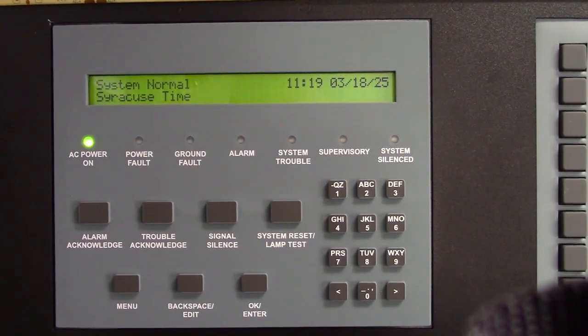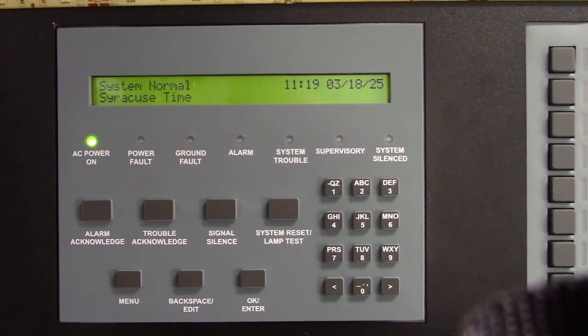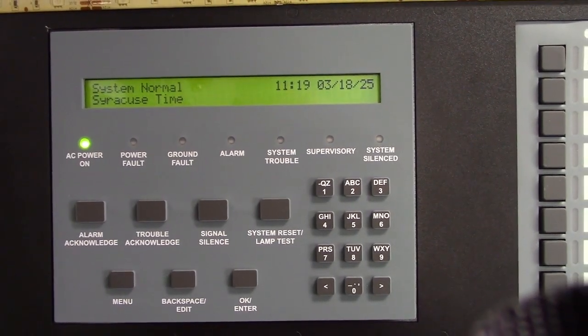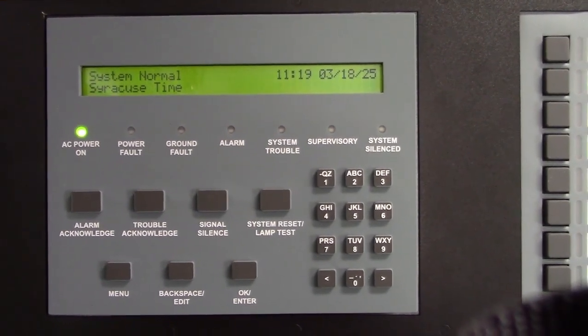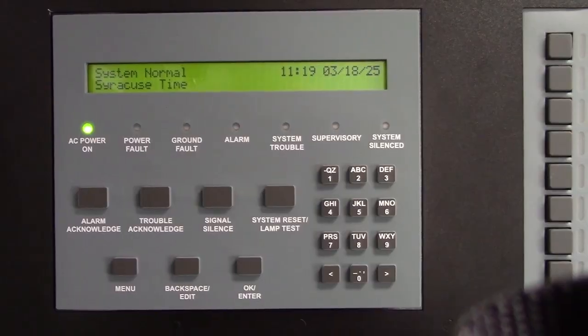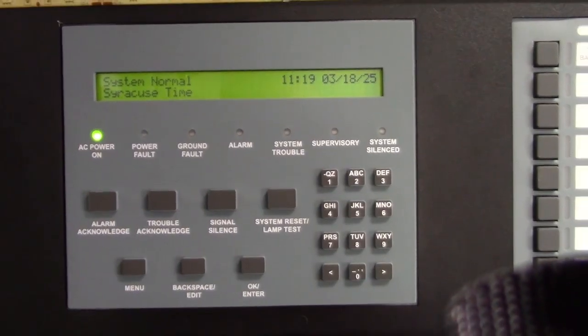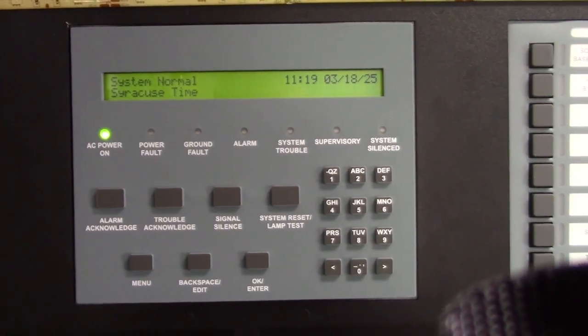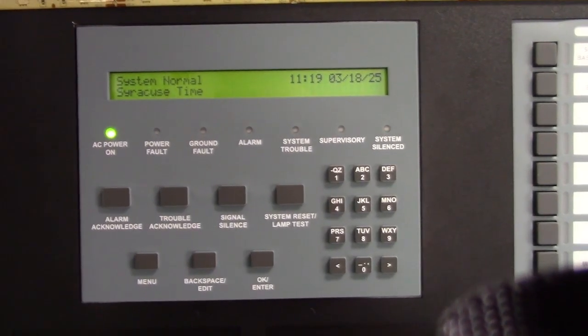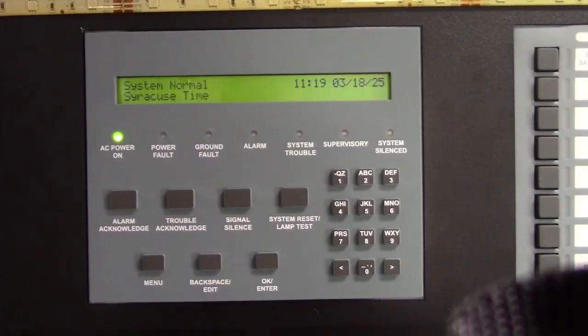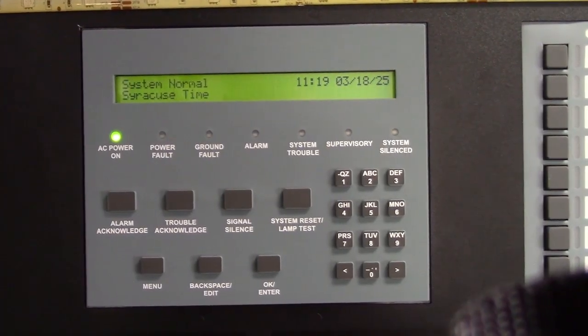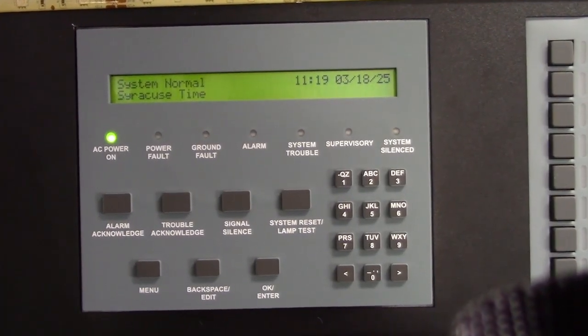The system restored to normal. And typically this does not happen instantly as soon as you clear the ground fault. So you need to be patient and double check things with your meter, which we will do very shortly.